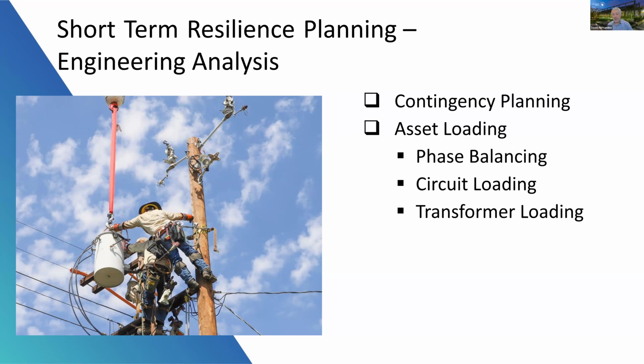From an asset loading standpoint, there's a number of things that we do annually ahead of each summer. One of those is phase balancing. Phase balancing is the process of trying to equalize the loads amongst the 3 phases so that we don't get high neutral currents, which could cause our protective relays to trip and cause an outage. Circuit loading, we review on an annual basis using our SCADA data, and also conductor loading using our grid analytics, which I'll talk about on the next slide.